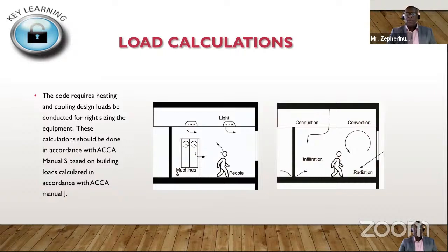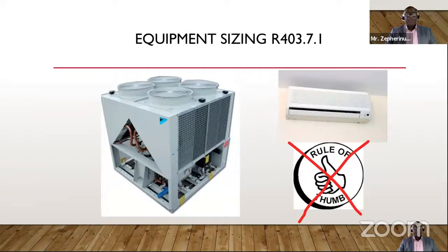radiation. So in designing your residential building, to right size the equipment and not to have oversized equipment that will use more energy, or equipment that is undersized so that it is not cooling effectively, the code requires that the calculations are done in accordance with the ACCA Manual S, based on the load calculated in accordance with the ACCA Manual J for your residential. And that's if you are designing a building that is going to be more than 50% air conditioned. So you have to get into more details as far as load calculations and more stringent measures for mechanical systems. So as I said, the rule of thumb method does not work.